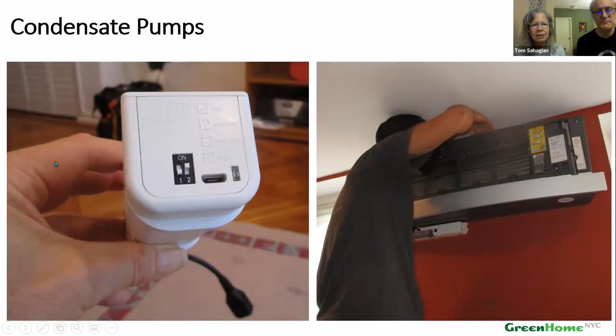The person who finally came and seems to have fixed it took out the condensate pump, cleaned the condensate pump filter, and changed the setting. He said he sets it on high, and they were all set on medium, which I think affects how quickly the water goes through. So we think that fixed it, but he came towards the end of the hot weather, so we'll see next summer if we have any more problems.